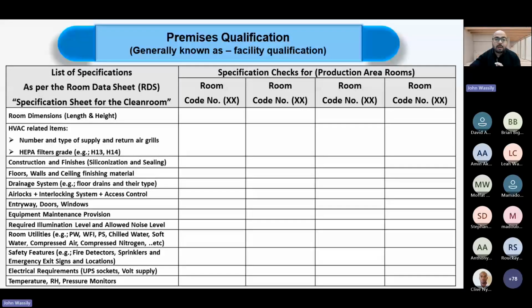For each room, we check the room dimensions, HVAC related items, the number and type of supply and return air grills, the HEPA filters and their grades, and the construction and finishes. All these are specifications for the rooms that should be listed in a room data sheet. Our role in facility or premises qualification is to make sure all the specs listed there are checked and fulfilled.